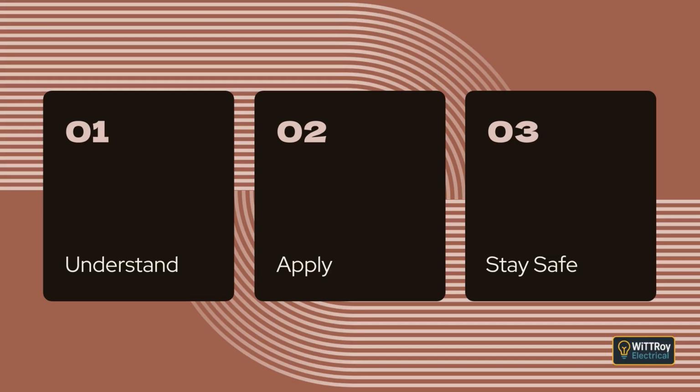Any time a cover is removed and live parts become exposed, the switchboard must have clear identification so people know the risks, following the rules in ASNZS 3439. Domestic switchboards do not use this exception. In homes, we never expose live parts.